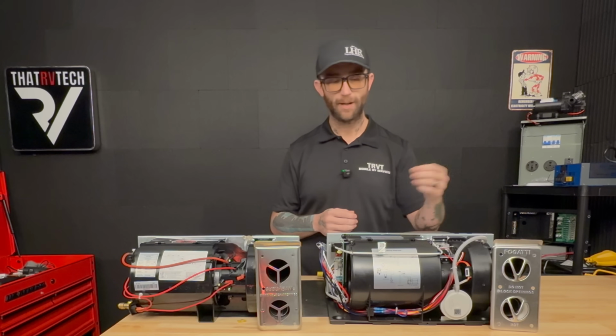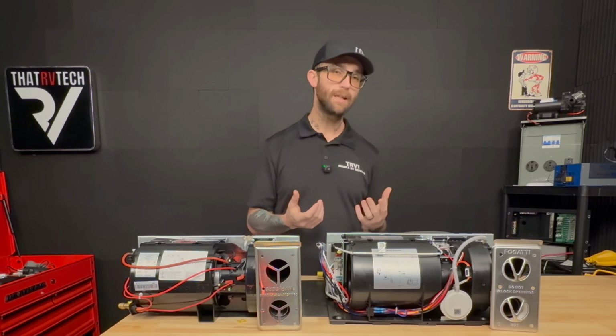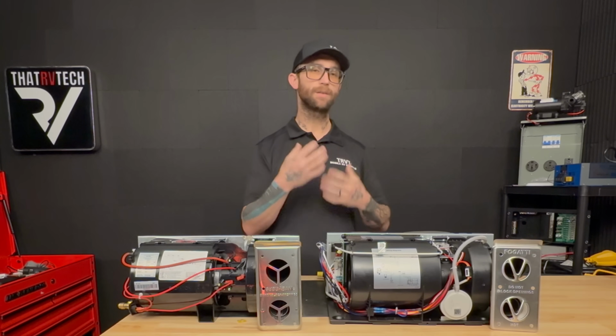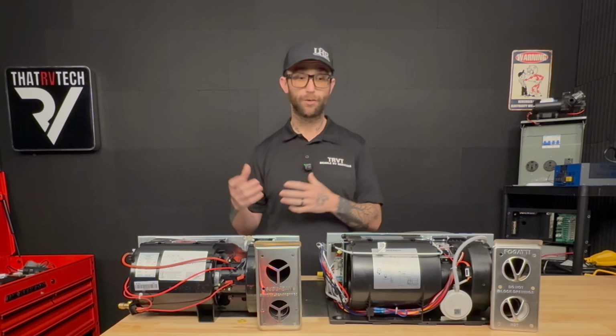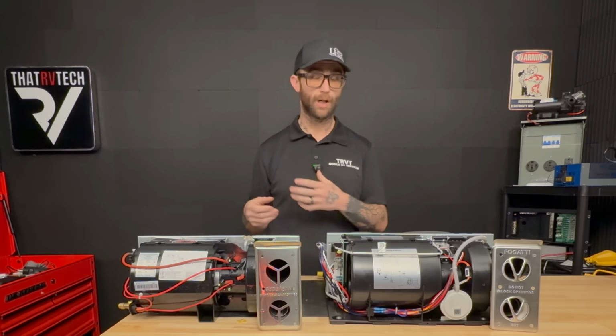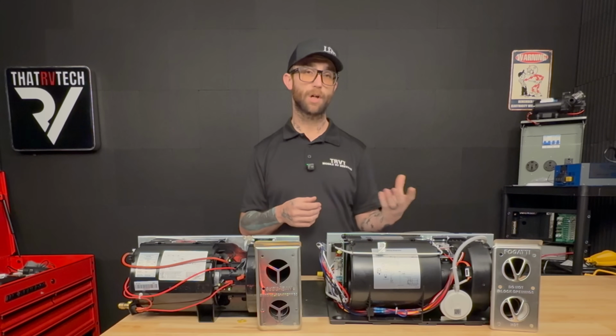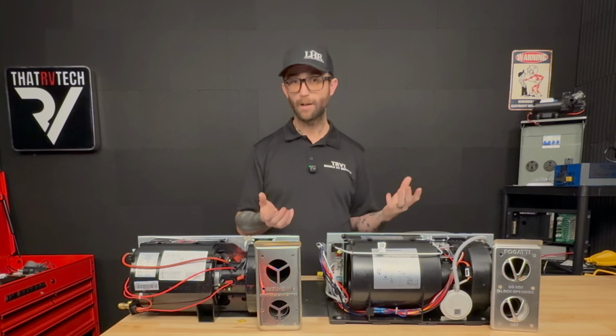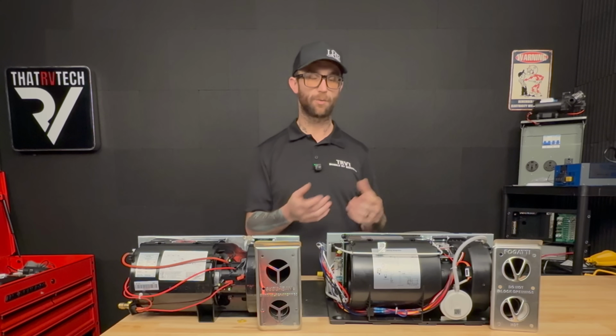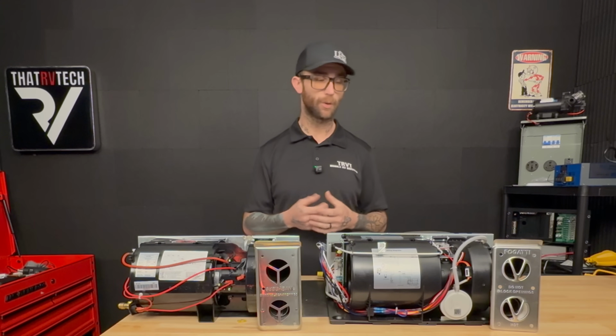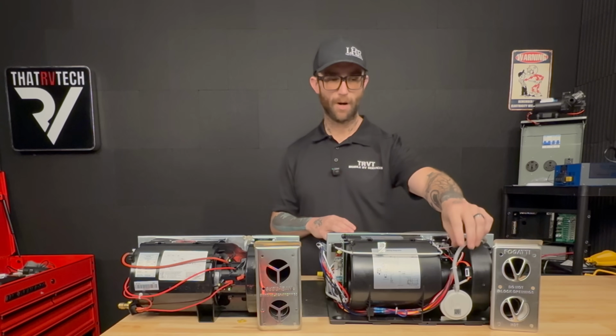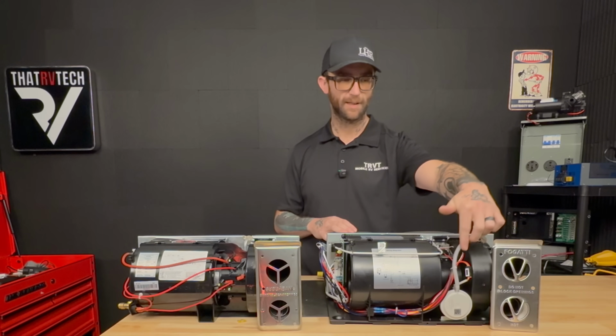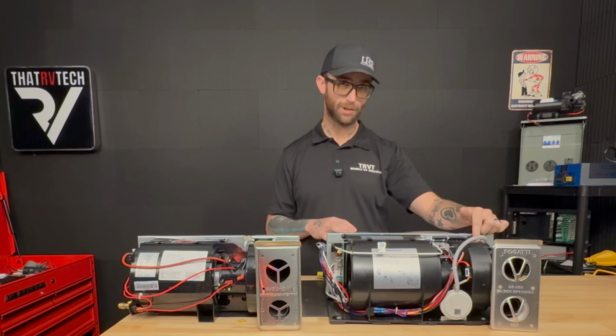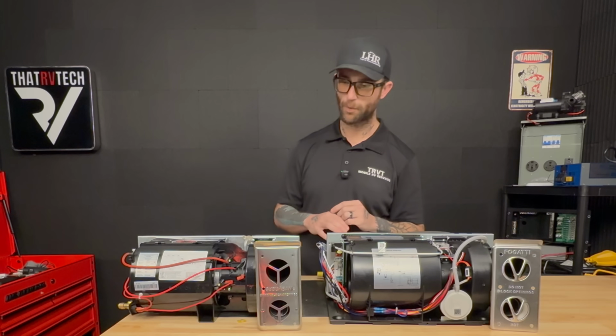This is a diaphragm style pressure switch, which means that no airflow is actually going through it. In other words, no pet dander, pet hair, dust, or debris are actually touching that switch. So we've already eliminated one of the biggest issues with the furnace, which is stuff getting stuck in the sail switch. And they achieve this by, again, running this small tube from the sensor over to the combustion chamber. I'm going to tell you why that's super important here in a sec.